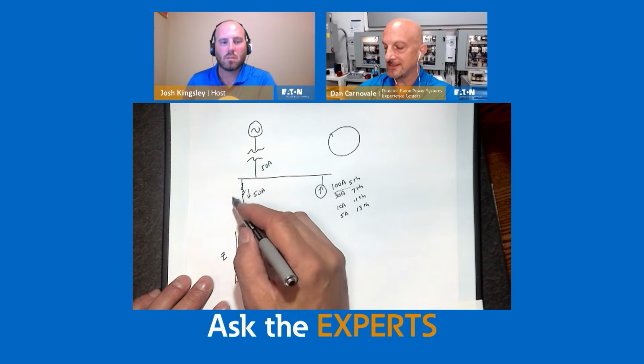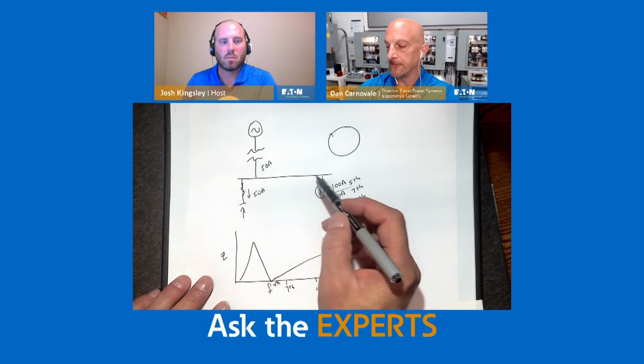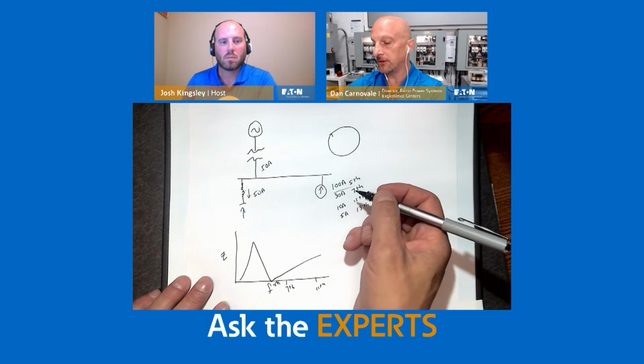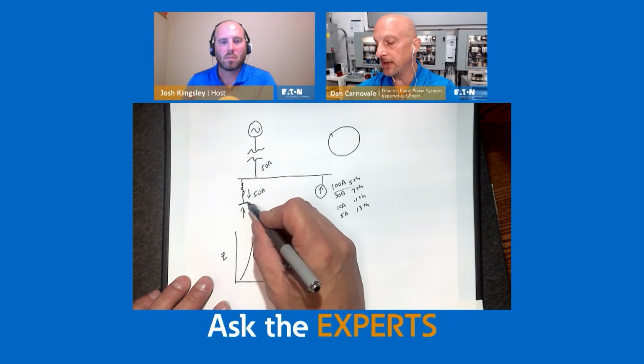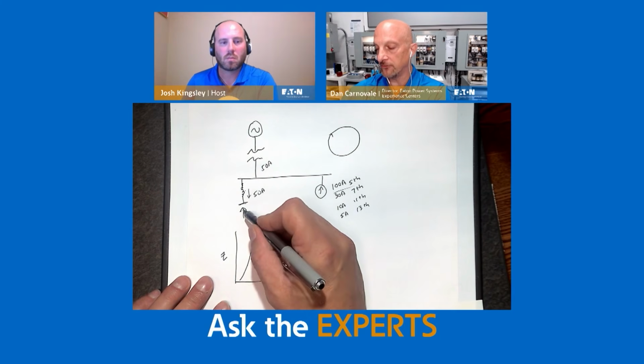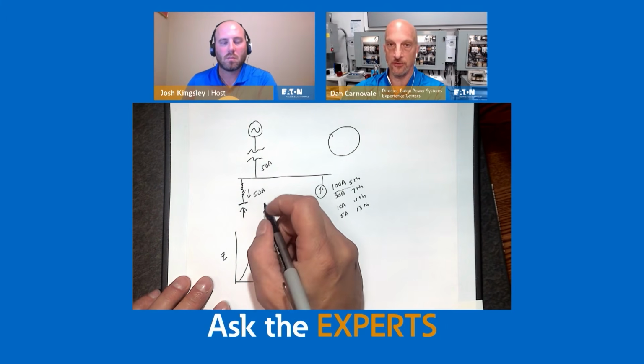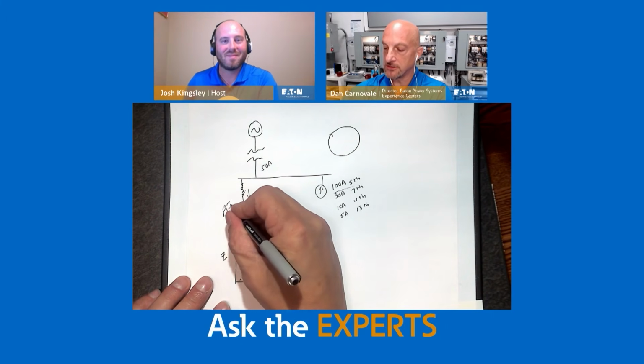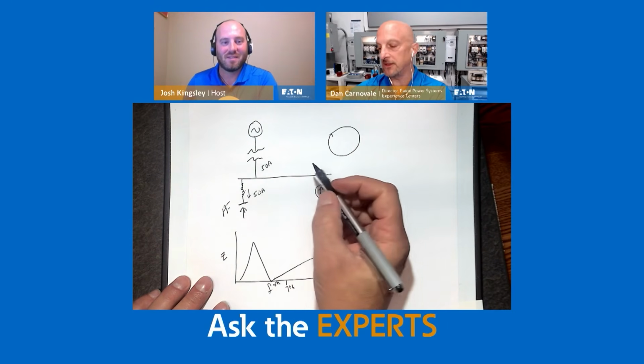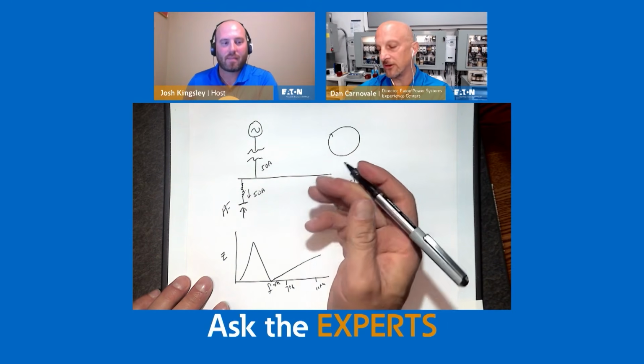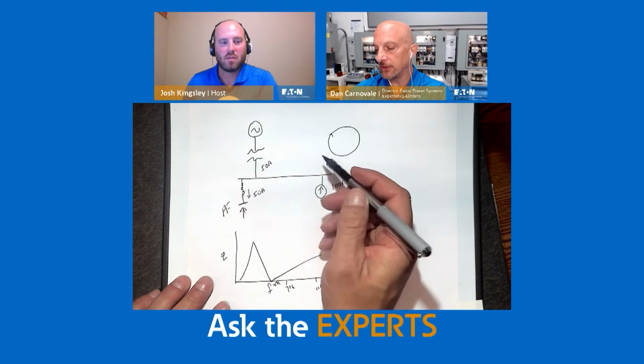But this takes a little bit more design, and you have to make sure that it's not going to be overloaded in the future. And honestly, the main benefit of a harmonic filter, believe it or not, is not harmonic filtering, it's power factor correction. So you size it usually for power factor, and then you get the benefit of harmonics. So we could talk about that more, but this is really kind of the key.